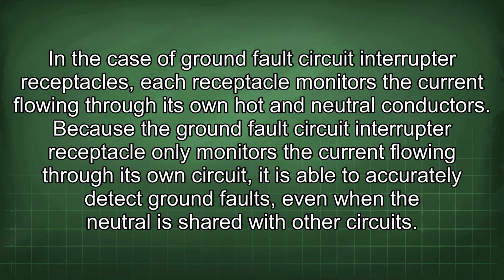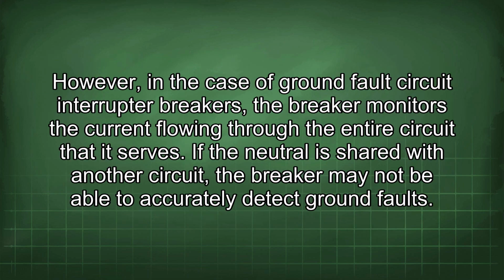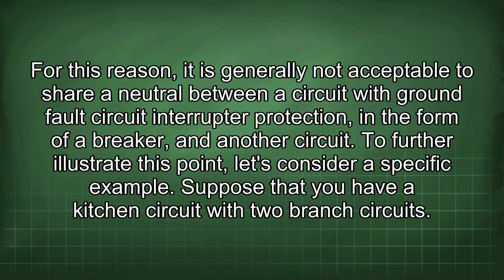In the case of ground fault circuit interrupter receptacles, each receptacle monitors the current flowing through its own hot and neutral conductors. Because the ground fault circuit interrupter receptacle only monitors the current flowing through its own circuit, it is able to accurately detect ground faults, even when the neutral is shared with other circuits. However, in the case of ground fault circuit interrupter breakers, the breaker monitors the current flowing through the entire circuit that it serves. If the neutral is shared with another circuit, the breaker may not be able to accurately detect ground faults. For this reason, it is generally not acceptable to share a neutral between a circuit with ground fault circuit interrupter protection in the form of a breaker and another circuit.